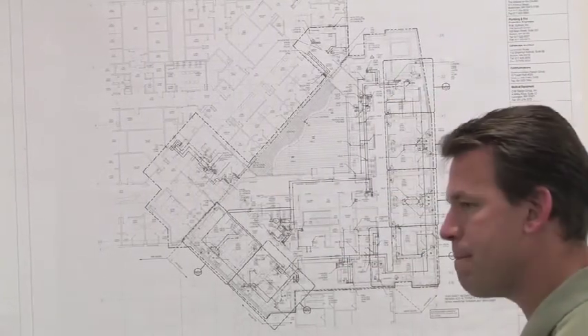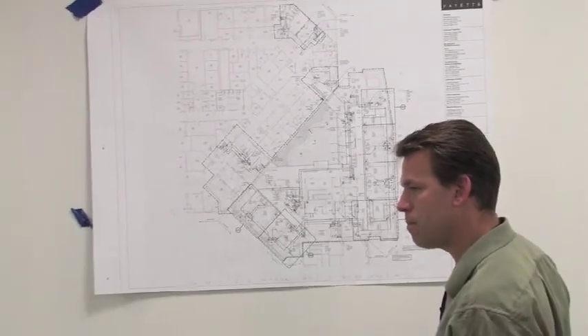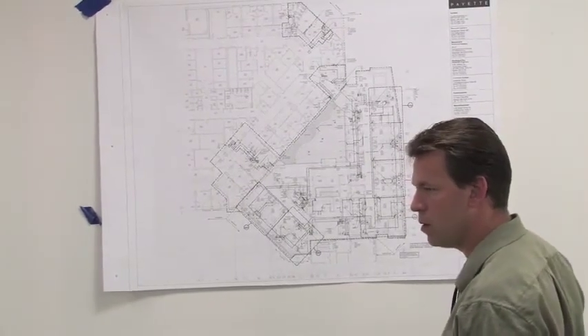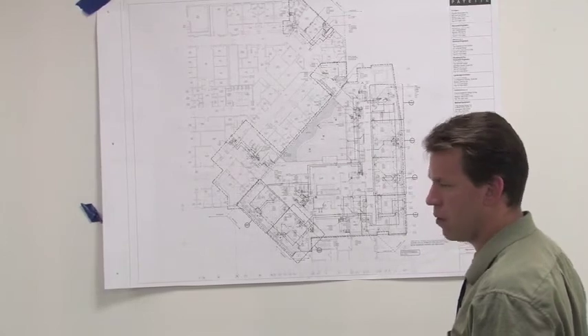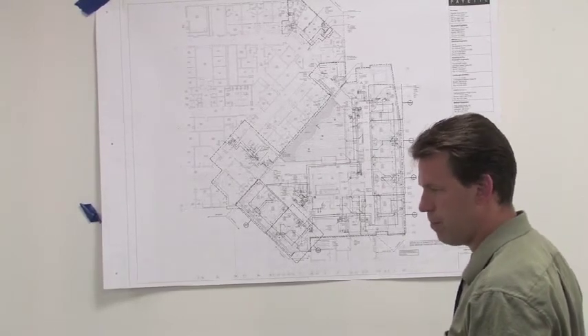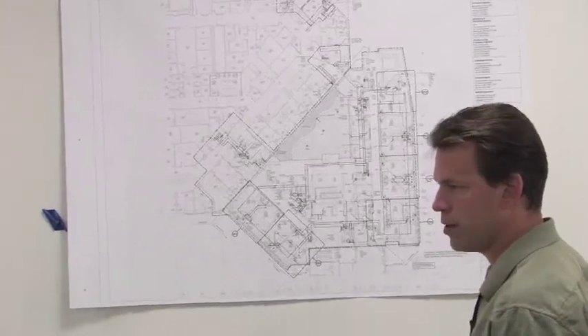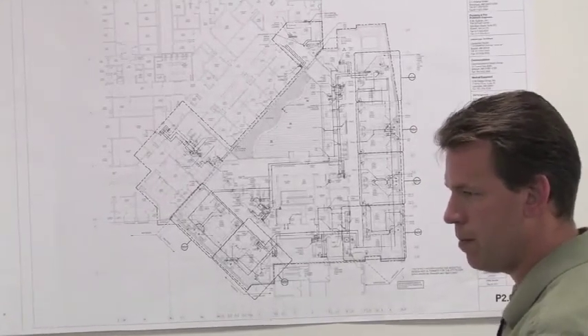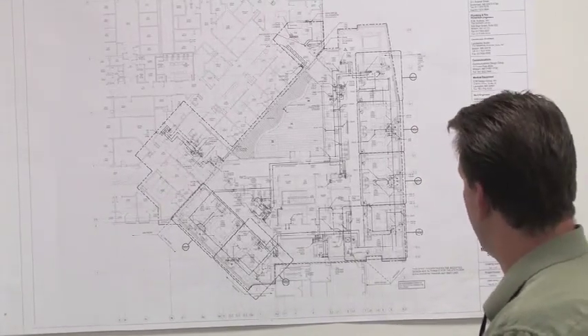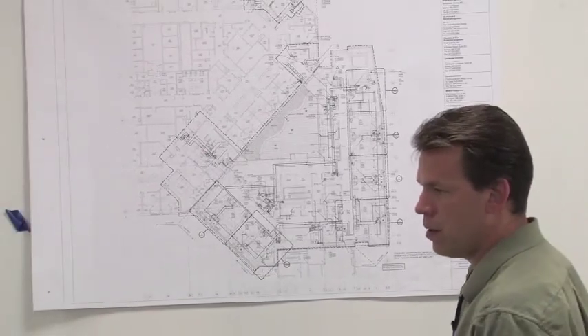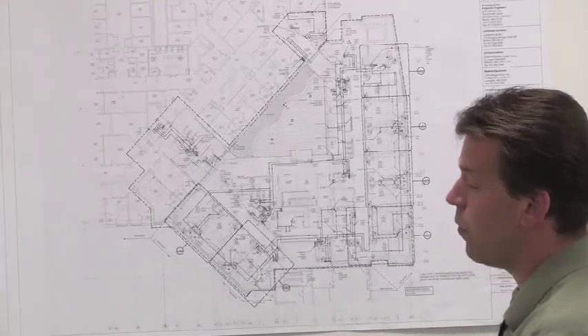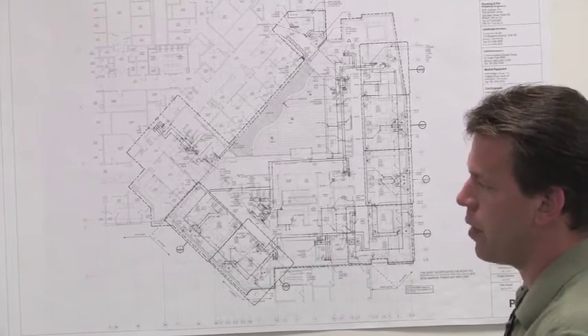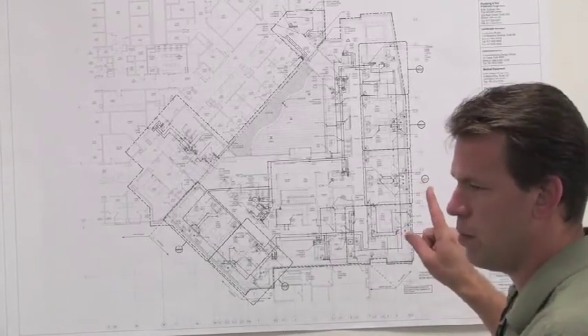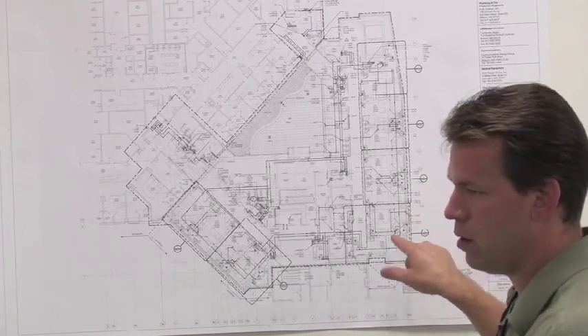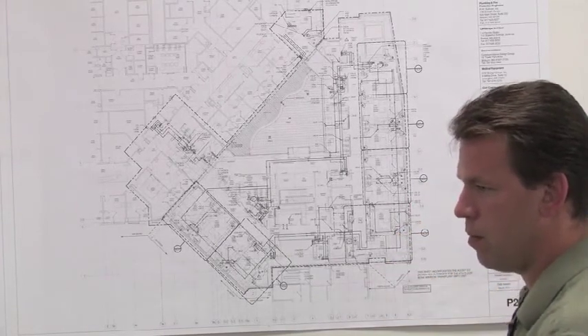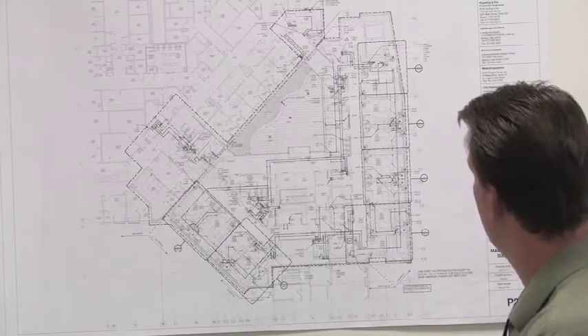So you treated the sixth floor the exact same way as we treated the main building sixth floor? Yes. We upfeed from the RO BMT to all the fixtures, through the walls, through a closed loop, no dead leg system, exactly. Dialysis boxes in there and all that kind of stuff? Yes, so it's pretty much a mirror image of what we're doing over in Main, except that in Main, dialysis boxes are not fed from this system, whereas here they are. Okay, that's something different. So dialysis boxes are not fed from the BMT system there?